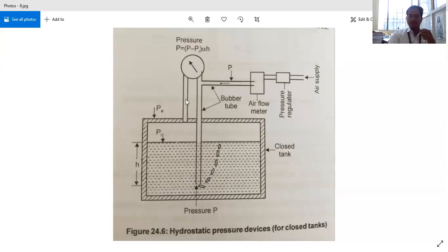directly proportional to the head of the water or the water level in the tank. So if this differential pressure value is decreasing, the head is also less. Say for some other purposes we are using this water, so the liquid level goes on decreasing. If it is about to reach this datum point, then the differential pressure recorded here will be zero.